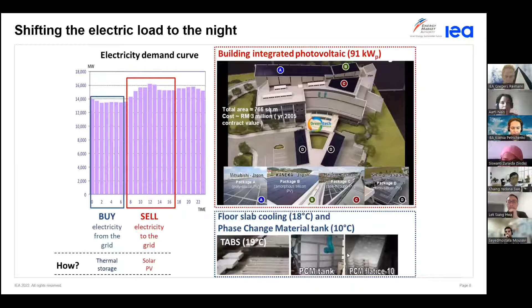The first cooling storage is a so-called phase change material tank, or PCM. You can actually buy these phase change materials or tanks with any melting point that you want. In this case, we decided on a 10-degree salt solution that freezes like ice, except it happens at 10 degrees. The reason we did that is it meant we could still use the same chiller, because we didn't have to go to an ice storage facility, which requires a different chiller and the use of glycol in some of the circuits.